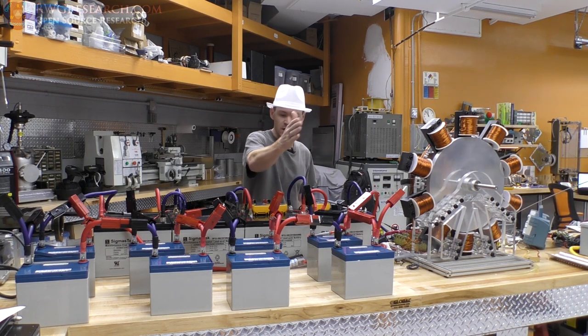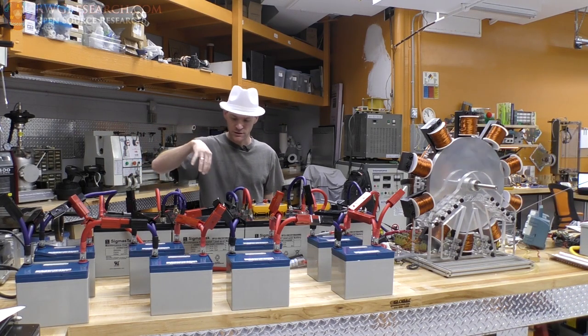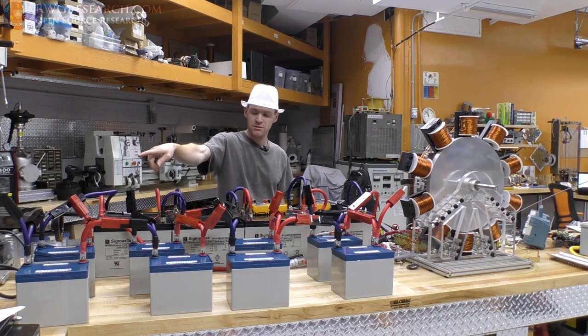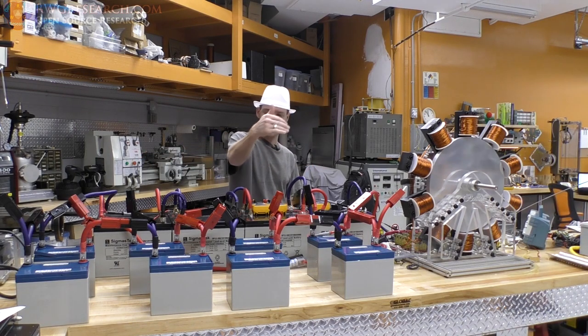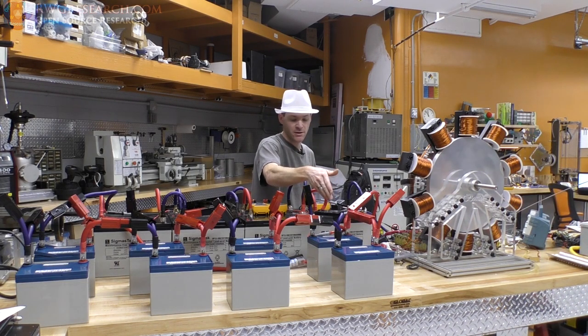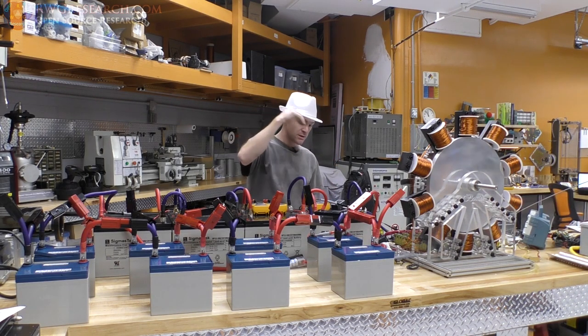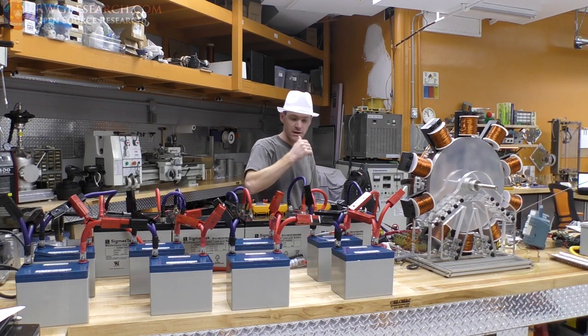I've got these in parallel, four banks of parallel, so eight total with all of them. Then these are in series and these are in series, so they're parallel series. They're 12 volts rated, 35 amp hour each, so that's 70 amp hour. Then these are 100 amp hour each, and they're 48 volts on each section.